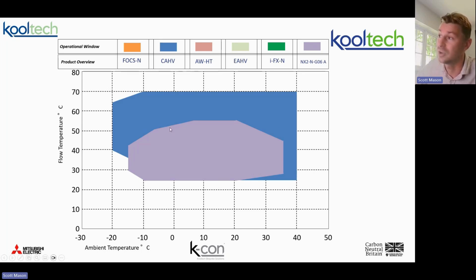Whereas if it was a high constant 50 degrees centigrade flow rate, that's bang in the middle of the CAHV's operating curve. So actually, the CAHV is going to give us probably an overall slightly better system efficiency at that point in time. So comfort zones are important. That also translates to longevity.